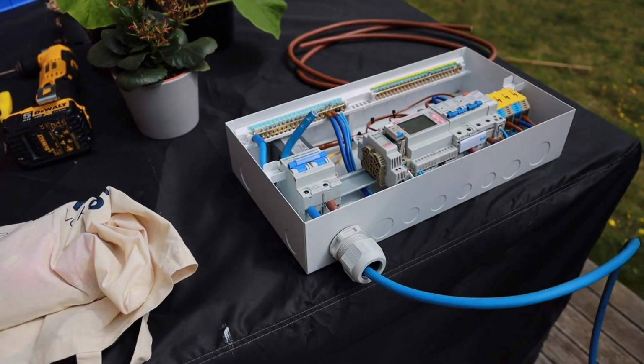So the solution was that we had to have an additional device installed in the home which basically capped our export limit, so that whatever happened, software glitches or just manual interventions, we would never be able to export more than 8 kilowatts at any one time onto the grid. Now that was done by a particular device which needed to be accredited. It also needed to be designed and manufactured as part of this whole trial. So again, you can understand that going from having a design on paper right through to getting it accredited so that it can be used within my home was a lengthy process, and that was another delay to this trial getting underway.